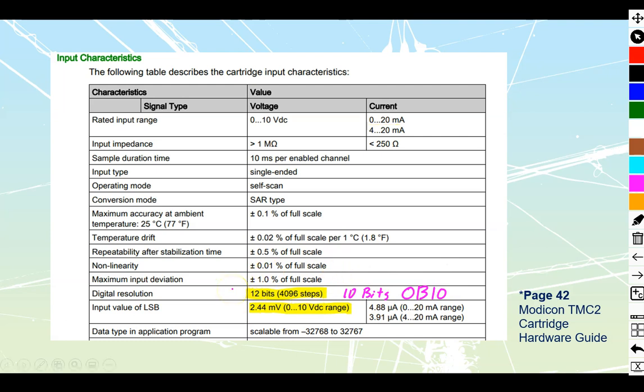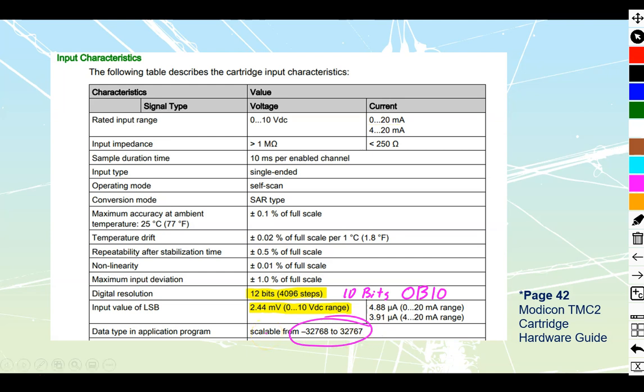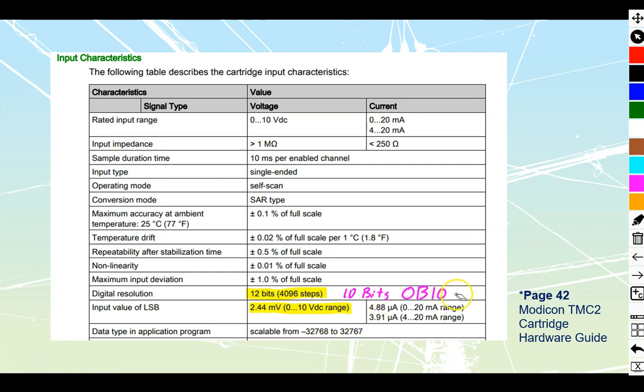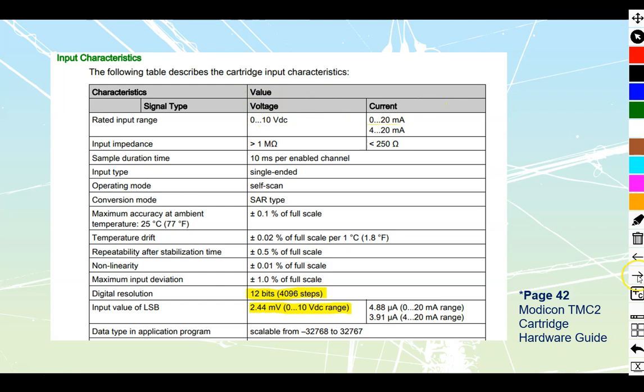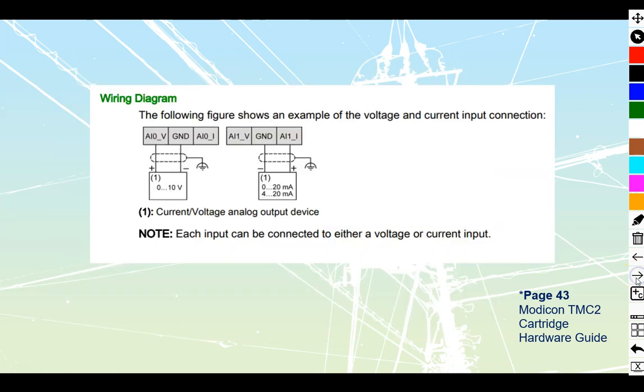You take all those bits coming in 4096 steps, and it's then going to allow you to scale that as raw data inside your PLC between negative 32,768 all the way up to positive 32,767. Don't forget there's the zero number in the middle—that's why those two numbers are slightly different. It's a decent input whether you're going with voltage or current.